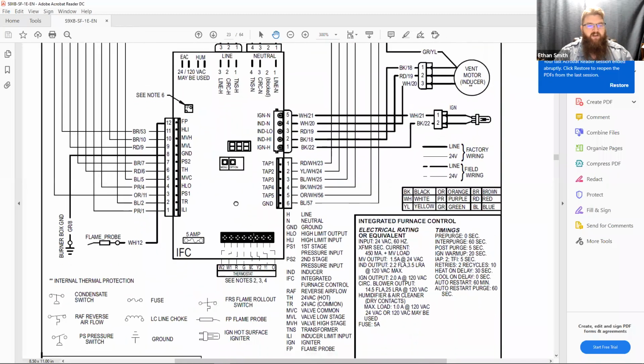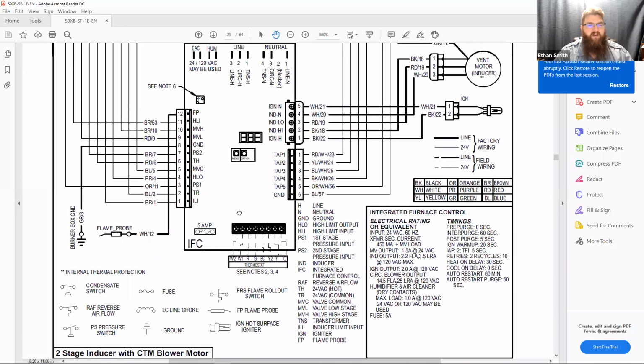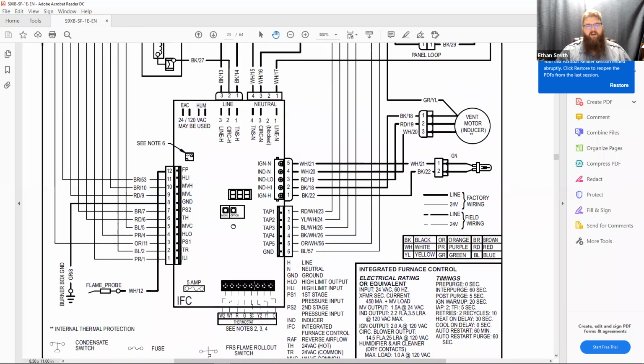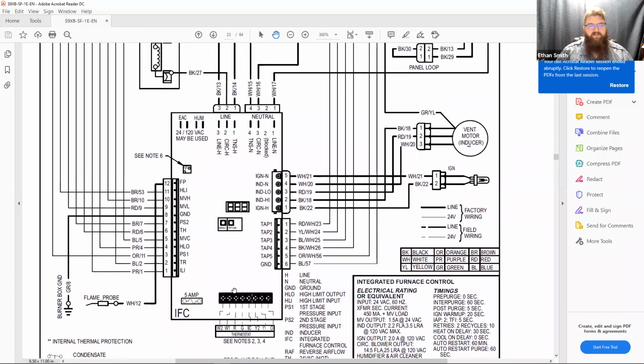Okay. So if we're going to go out and do a diagnosis on this, and this does require you to understand a little bit about sequence of operation, we can first check to make sure that our furnace is getting a call for heat. So we can check for voltage between W1 and my common wire, which is this BC terminal here. Okay, that tells me that the switch in the thermostat has closed if we've got 24 volts between W1 and common. So if we see 24 volts there, we know that the thermostat's calling for heat. At that point, we can start tracking down our sequence of operation.